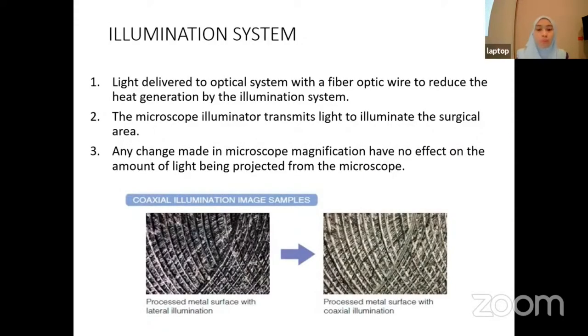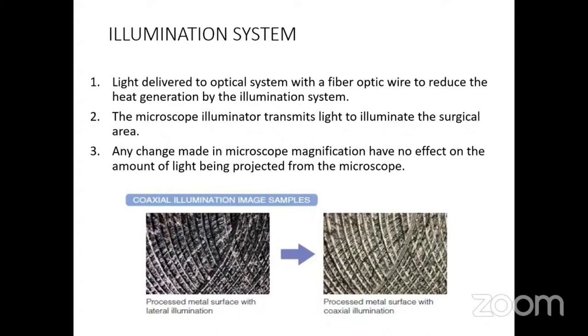Now we go to the illumination system. The light is delivered to the optical system via a fiber optic wire to reduce heat generation by the illumination system. The microscope illuminator then transmits light to illuminate the surgical area. Any change made in the microscope magnification has no effect on the amount of light projected. This image shows how, when using coaxial illumination, the image will look clearer and sharper compared to lateral illumination.